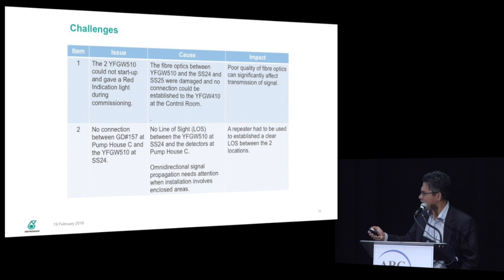The other problem that we encountered during that time was no connection between the gas detector pump house and the transmitter receiver at the substation, because of no line of sight. So the way forward was: omnidirectional signal propagation needs attention when installation involves enclosed areas. We need to really make sure of the line of sight. The way we solved this problem is to install a repeater to establish a clear line of sight between the two locations. So we need a repeater to boost the signal.